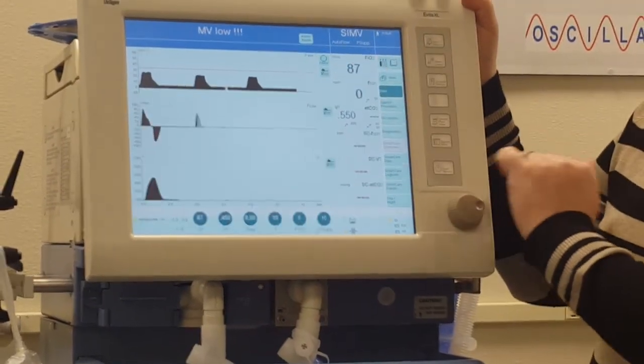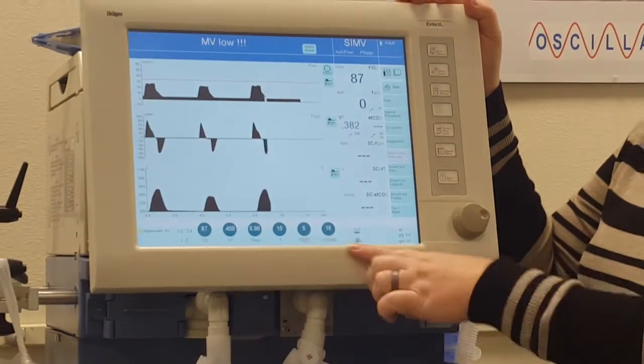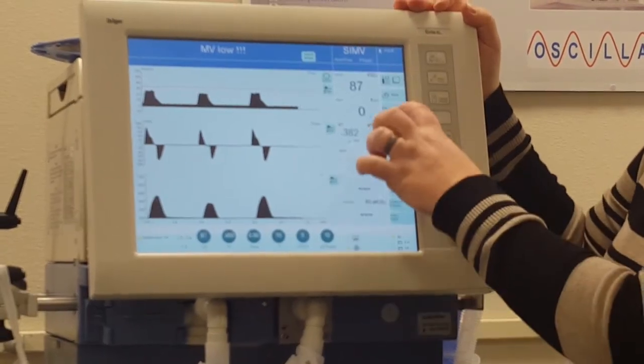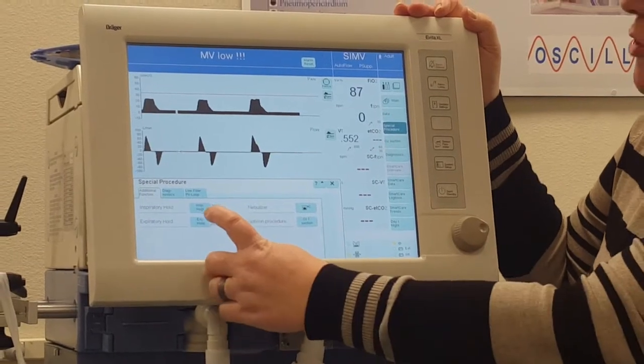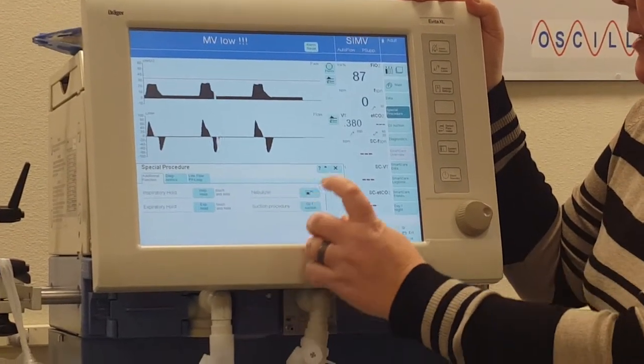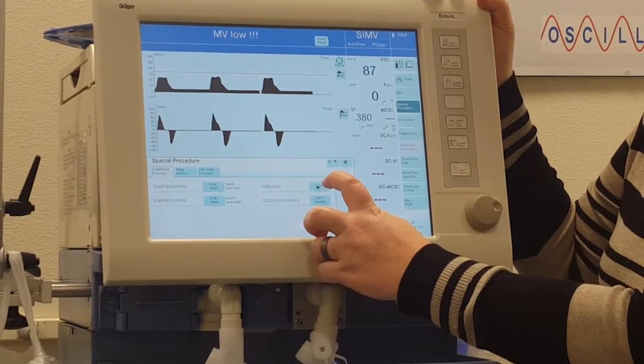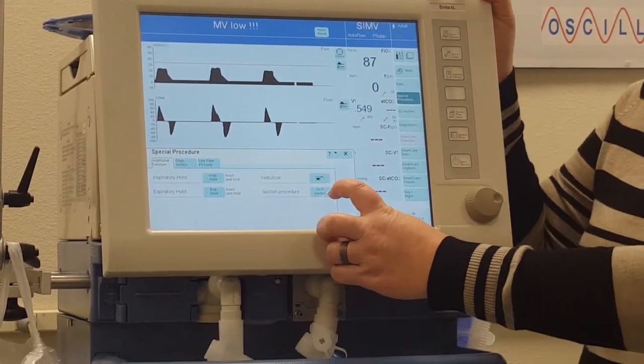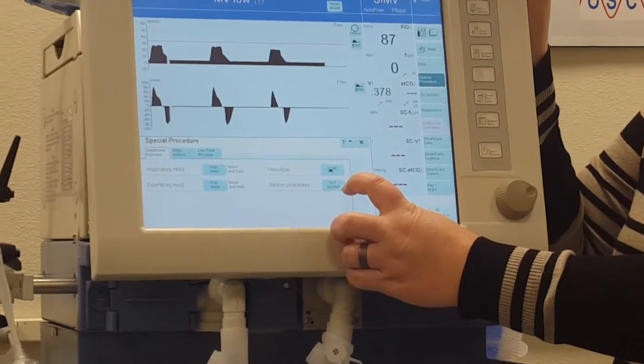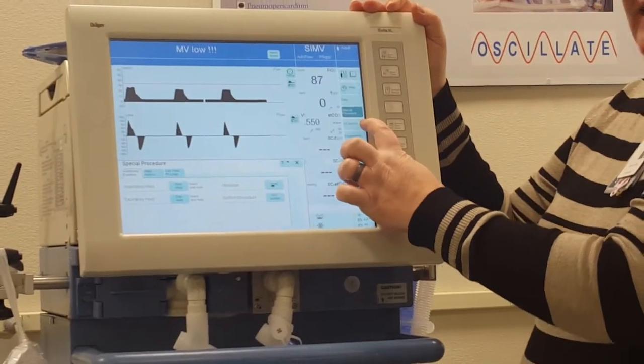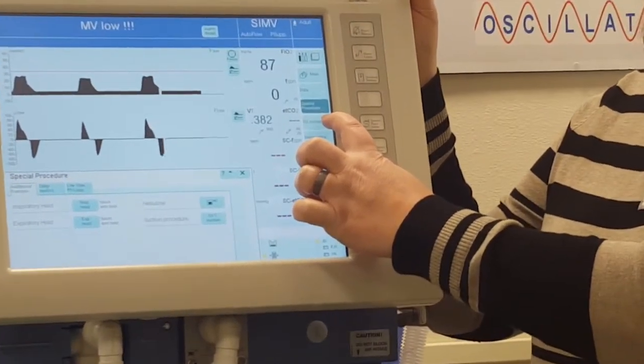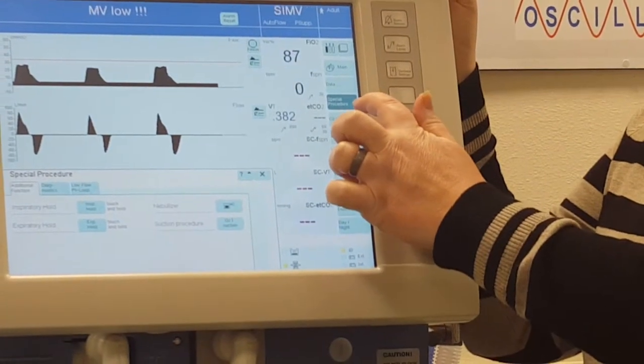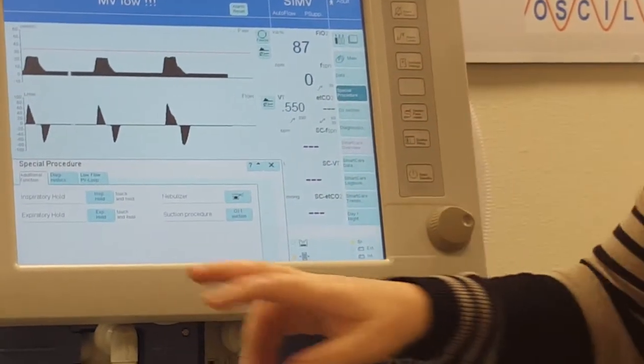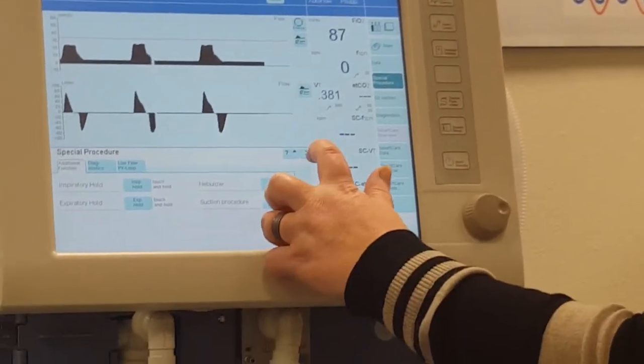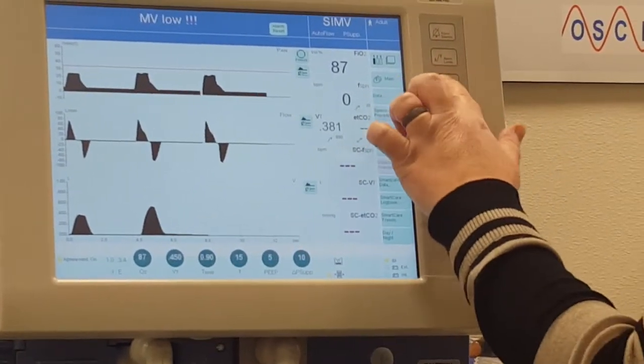Main will always take you back to the main screen, which is where the waveforms and the quick access buttons are. Special procedure will get you to inspiratory hold, expiratory hold, nebulizer if you wanted to run the nebulizer, and O2 suction, so that would be if we're going to suction our patient and we want to give them 100% oxygen. I got there by going to special procedures, but there's also a quick access key for O2 suction right there because it's used all the time. So this is where you'd probably get it from, but you can also get it from here. So if I'm going to do, well, I'm going to turn my DRVC off, so hold on a second.